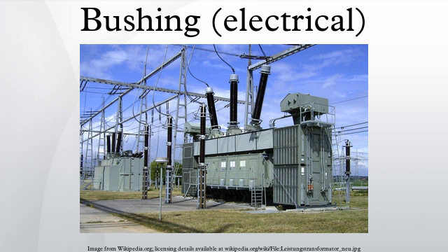Bushing failure. Bushings sometimes fail due to partial discharge. This is sometimes due to the slow and progressive degradation of the insulation over many years of energized service. However, it may also be a rapid degeneration which destroys a good bushing in a matter of hours.